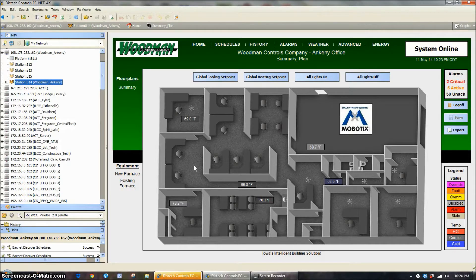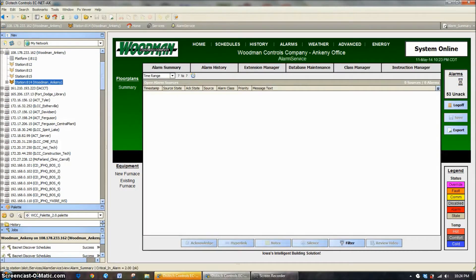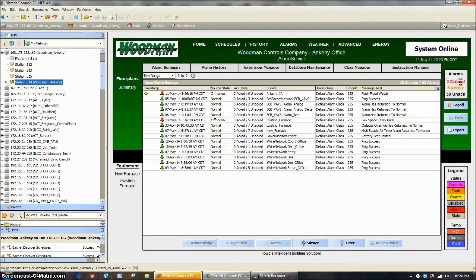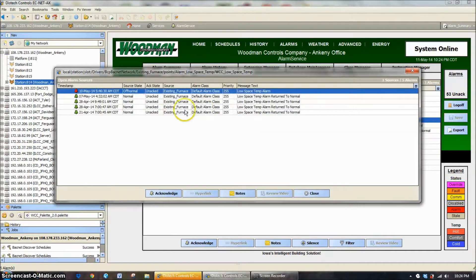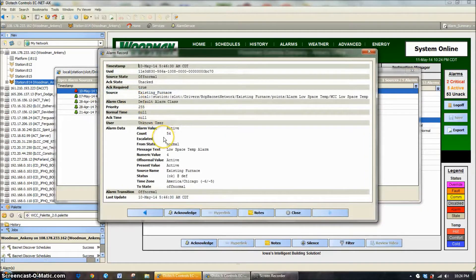In this example, we're just using my office. The alarms on the right-hand side are showing that we have two critical alarms, and one is a low space temperature alarm on the existing furnace. We're going to use this point and this alarm extension because we know it's been a nuisance. Opening that with a double-click, we can see already right here on May 10th, this alarm's gone in and out of alarm 54 times, which is a fairly large number. We don't want something doing this every night or every morning or even once a week if it doesn't need to be.